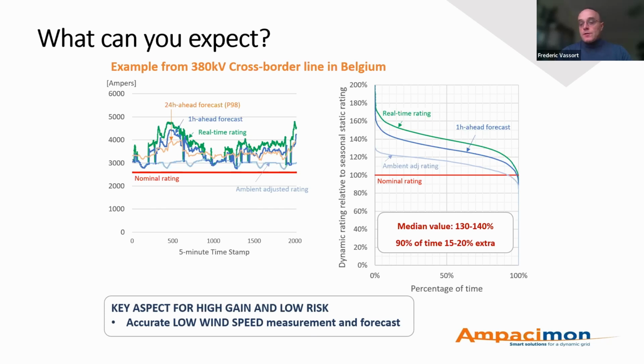On the right side of this page is just a different way to plot the data. You can see that the mean value in this example is around 130 to 140% of the nominal rating of the line, in that indeed 90% of the time there's somewhere between 15 to 20% of extra capacity available. What is really important, and I want to stress that, is that to be able to take advantage of that, you need to monitor the line properly with sensors. That's what we do at Ampacimon, to make sure that you do capture properly the critical parameters of these lines, and in particular that the wind speed is properly measured, particularly at low wind speeds.